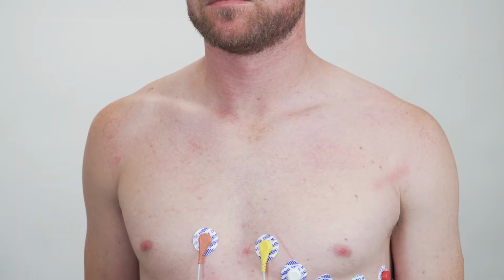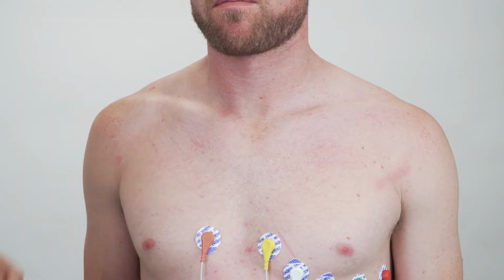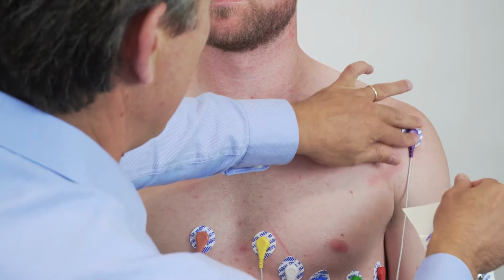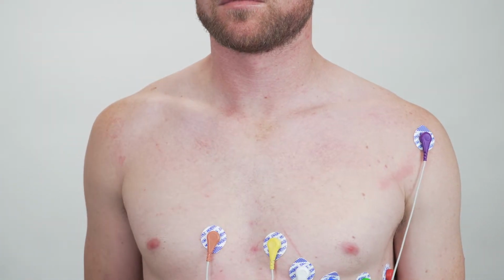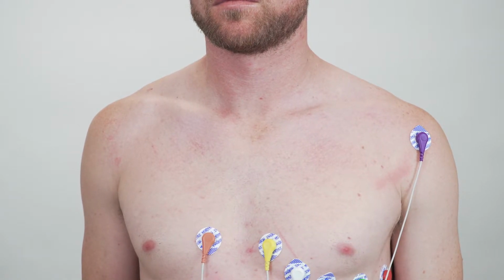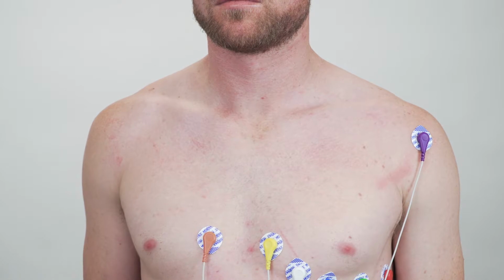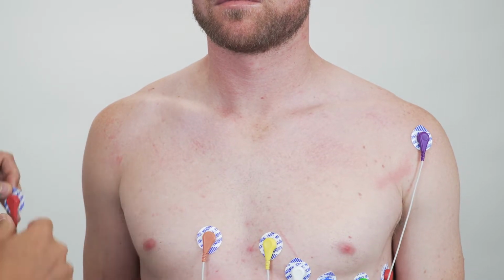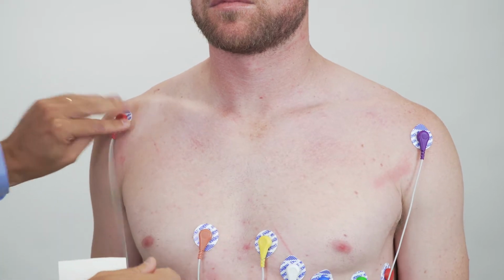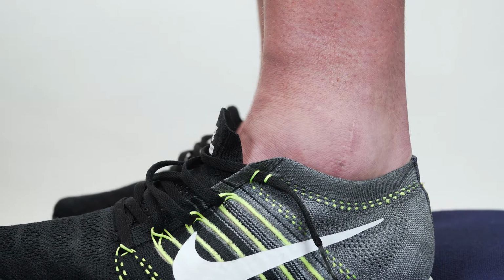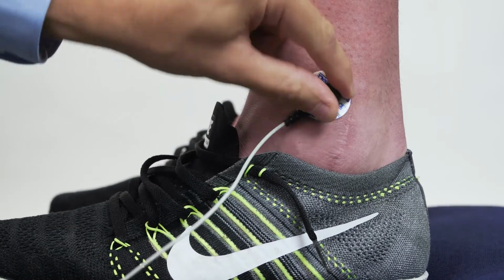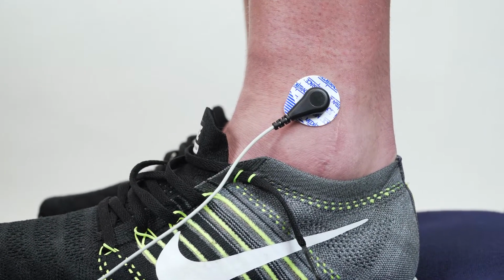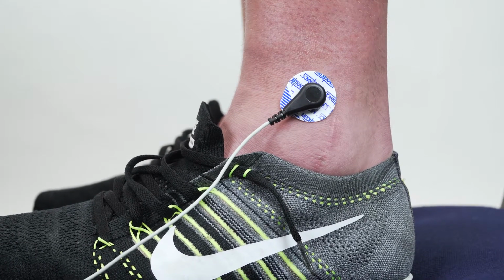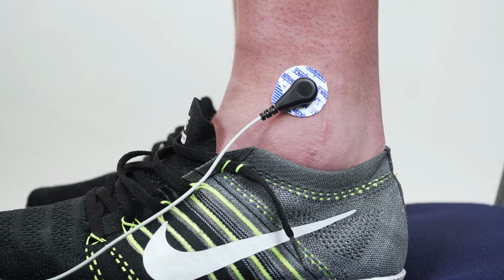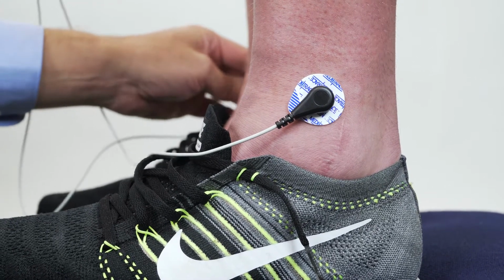Right now we're going to stick on the limb leads for lead 1 and lead 2. So we're first going to stick on left arm and try and stick it on somewhere where there is not a lot of muscle or muscle movement, because that'll just cause EMG. Then we're going to put on right arm, and then we can connect the left leg, which is the reference for all the augmented leads. And lastly, we can stick on the common, which goes to the ground input on the Octal Bio Amp. Stick that on the right leg.